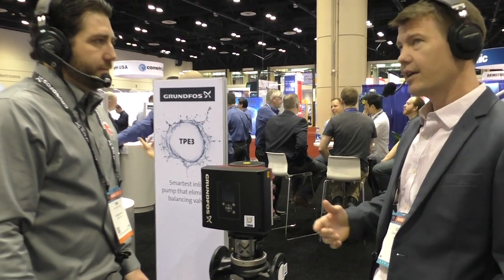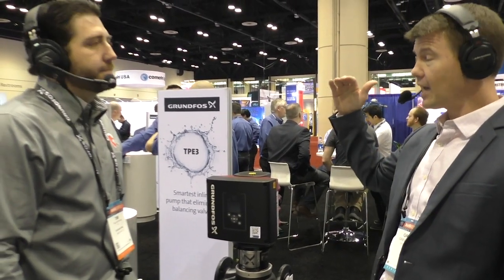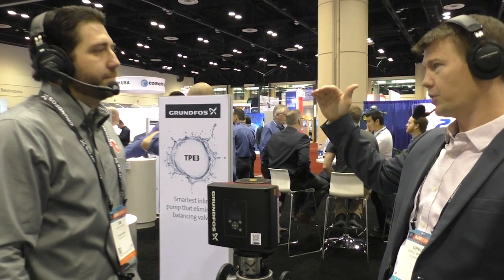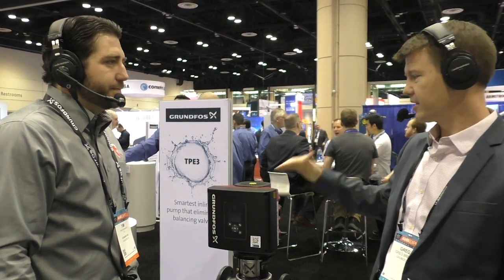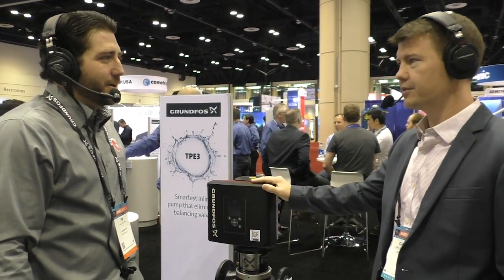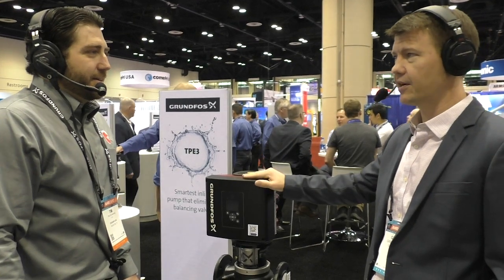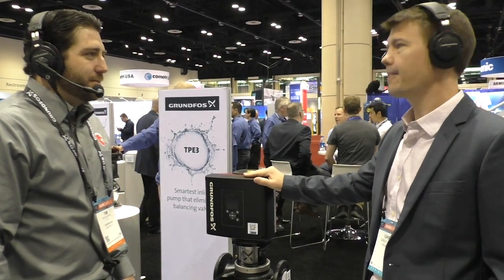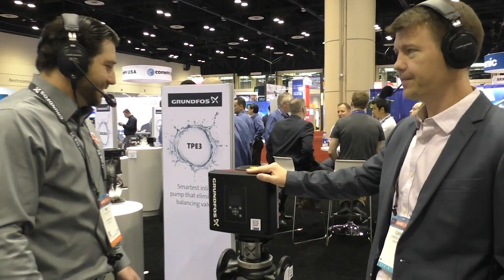So the hydraulic DOE PEI limit is 1.0, with a lower number being better. This pump is in the 0.2 range — the most efficient pump out there, meaning it's 80% better than the bar.